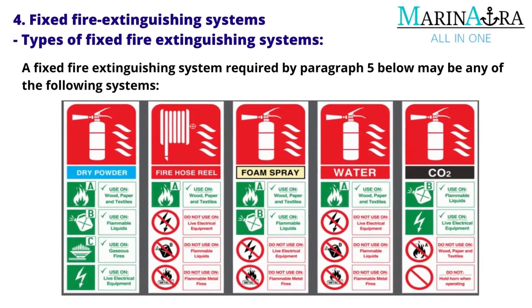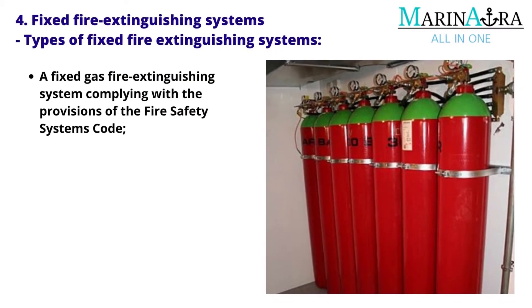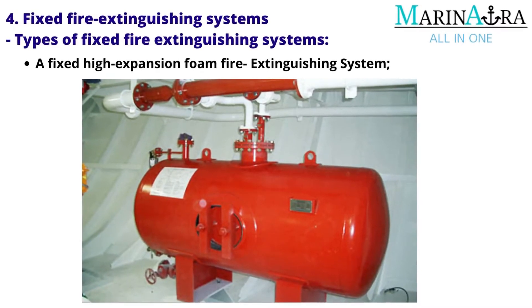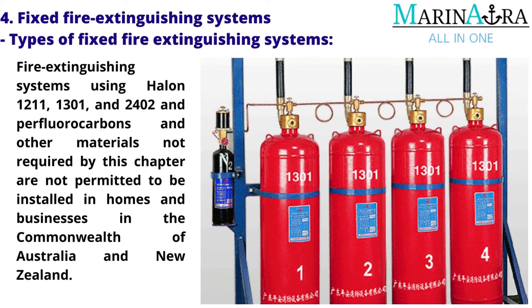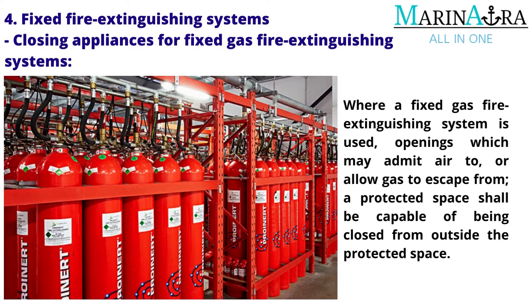Fixed fire extinguishing systems: A fixed fire extinguishing system required by paragraph 5 may be any of the following: a fixed gas fire extinguishing system complying with the provisions of the Fire Safety Systems Code; a fixed high expansion foam fire extinguishing system; or a high-pressure water spraying fire-extinguishing system. Fire extinguishing systems using Halon 1211, 1301 and 2402 and perfluorocarbons are not permitted to be installed. Closing appliances for fixed gas fire extinguishing systems: Where a fixed gas fire extinguishing system is used, openings which may admit air to or allow gas to escape from a protected space shall be capable of being closed from outside the protected space.